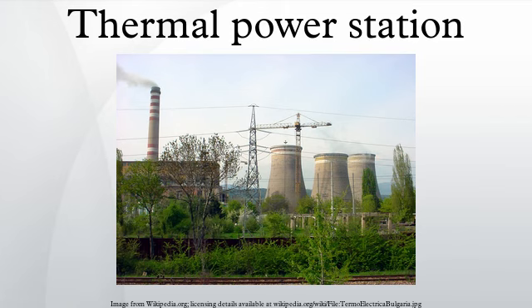Feed water heating and deaeration. The boiler feed water used in the steam boiler is a means of transferring heat energy from the burning fuel to the mechanical energy of the spinning steam turbine. The total feed water consists of recirculated condensate water and purified makeup water. Because the metallic materials it contacts are subject to corrosion at high temperatures and pressures, the makeup water is highly purified before use.